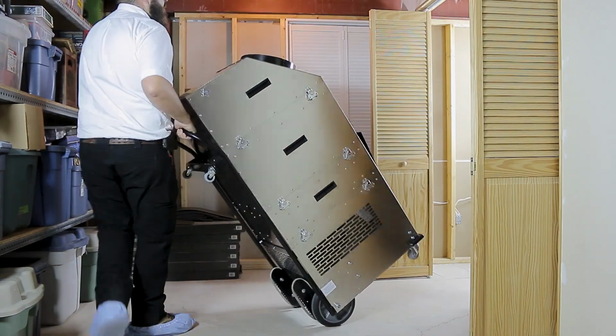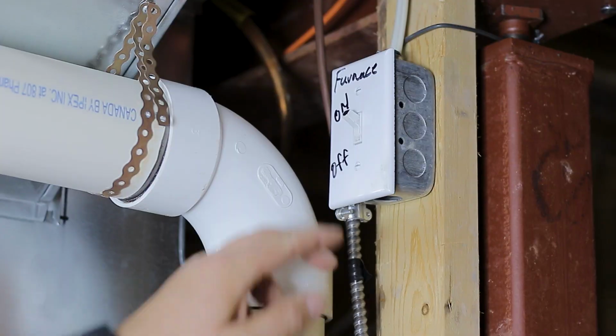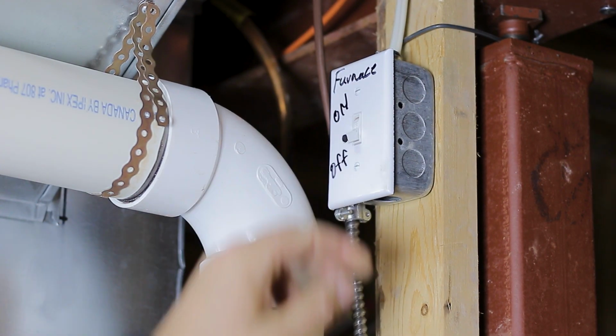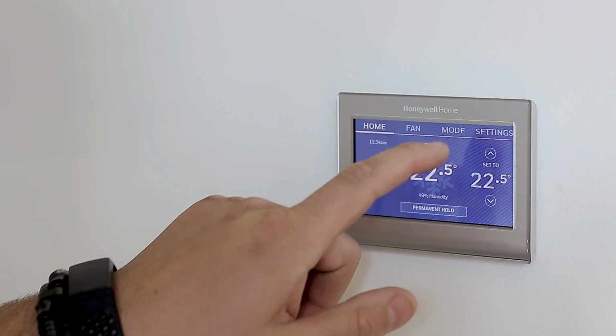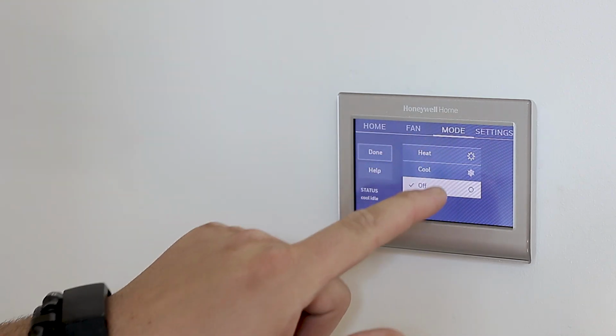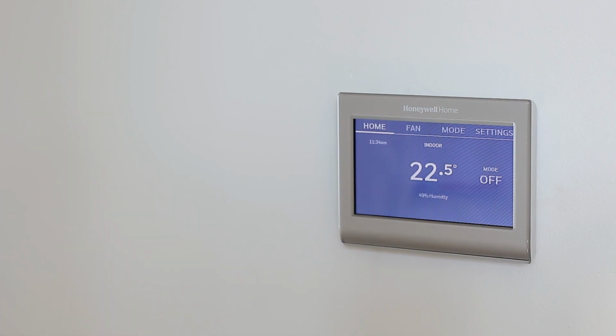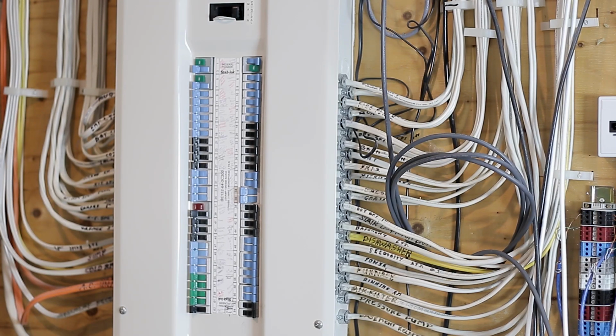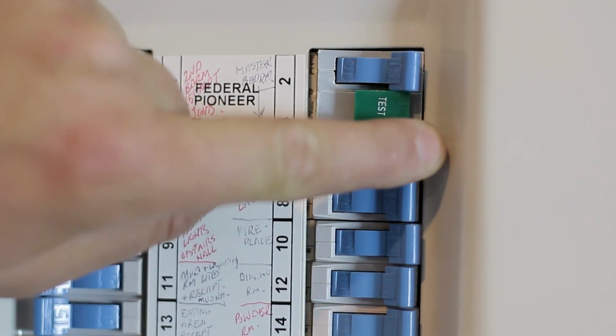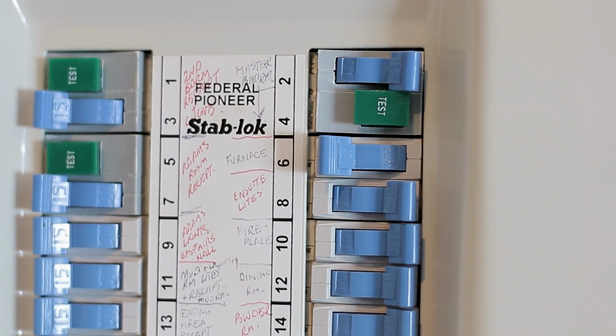Before doing anything to the furnace, AC, or duct system, be sure the system is turned off and will not automatically turn on when working on it. It's good practice to also turn the air handling unit off at the thermostat as well as the circuit breaker to prevent accidental startup. Be sure to comply with all local regulations regarding gas pilot lights and other utilities.